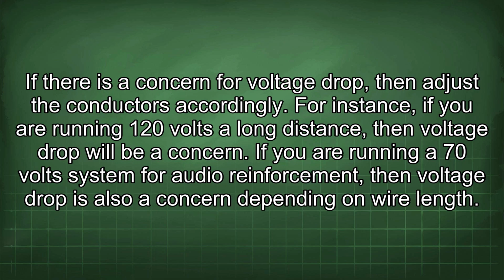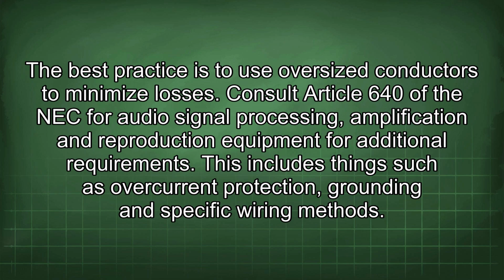For instance, if you are running 120 volts a long distance, then voltage drop will be a concern. If you are running a 70-volt system for audio reinforcement, then voltage drop is also a concern depending on wire length. The best practice is to use oversized conductors to minimize losses.